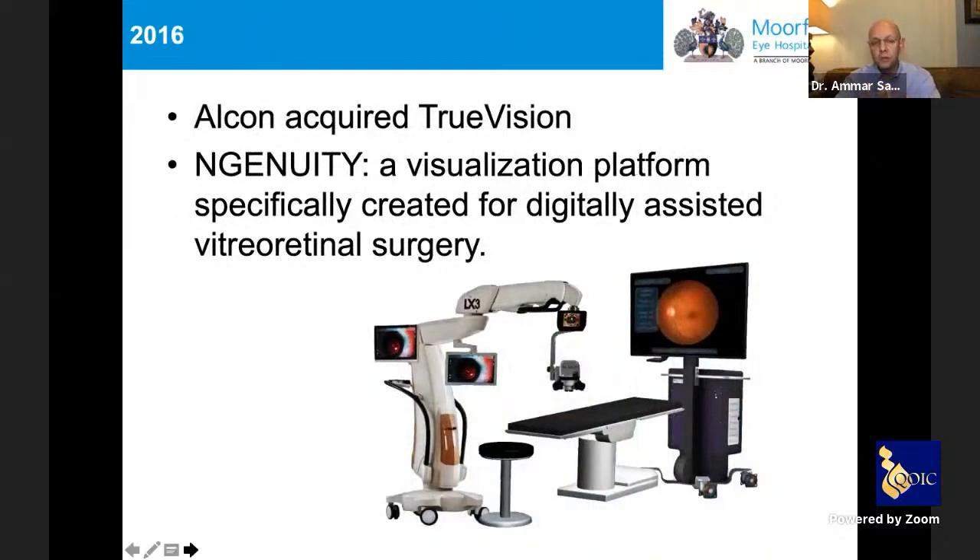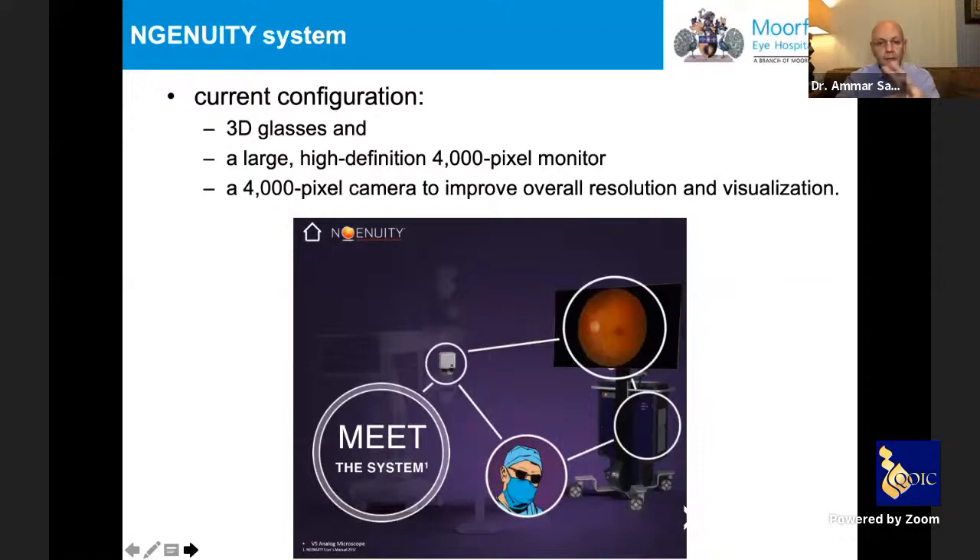Alcon acquired TrueVision in 2016 and created the system we currently call NGENUITY — a visualization platform specifically designed for ophthalmology, mainly vitreoretinal surgery, later branching into anterior segment. The system has three components: a large 4K high-definition monitor, a 4K high-dynamic-range camera connected to the microscope, and a processor that elevates image intensity, allowing the use of much dimmer illumination while maintaining excellent visualization.